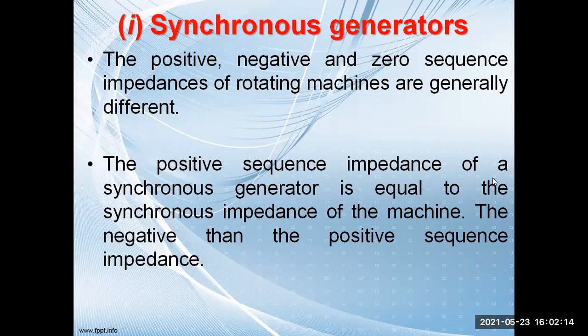So that is the way we can calculate the synchronous impedance. Now this synchronous impedance, whatever you have calculated in electrical machines, will be equal to the positive sequence impedance of the synchronous generator. So in the power system, this positive sequence impedance will be equal to the synchronous impedance of the machines.